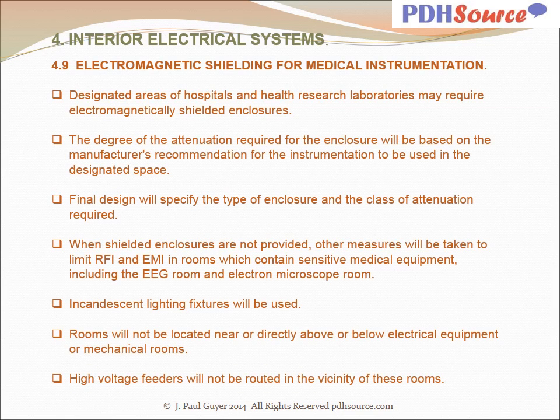Designated areas of hospitals and health research laboratories may require electromagnetically shielded enclosures. The degree of the attenuation required for the enclosure will be based on the manufacturer's recommendation for the instrumentation to be used in the designated space. Final design will specify the type of enclosure and the class of attenuation required. When shielded enclosures are not provided, other measures will be taken to limit RFI and EMI in rooms which contain sensitive medical equipment, including the EEG room and electron microscope room.